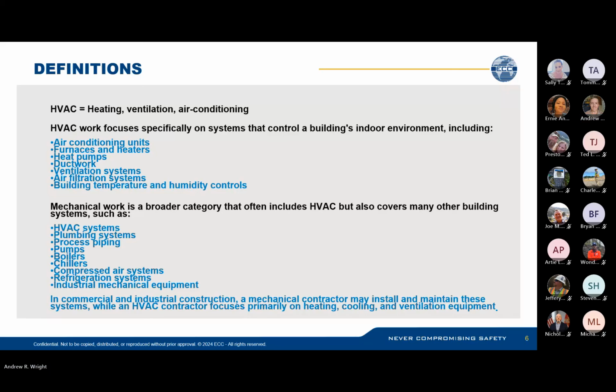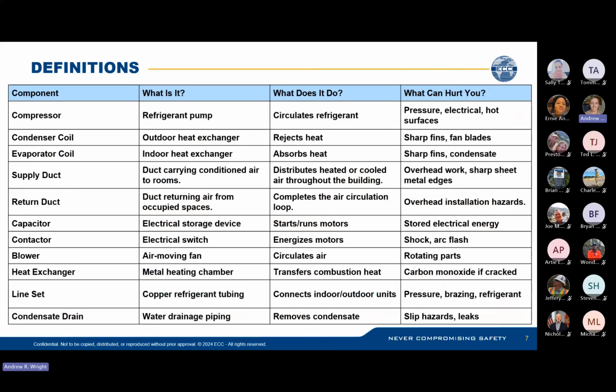I'm a big believer that you have to actually know what you're looking at and understand the systems being installed or worked on to be effective at your job as a safety professional. There are some terms I'm going to throw out there, and forgive me if you already know them, but it's important to understand what they do and what could actually hurt you. A compressor is essentially a refrigerant pump. It's how the refrigerant gets compressed and can release heat. Basically, it circulates refrigerant, and what could hurt you there is pressure, electrical, and hot surfaces.